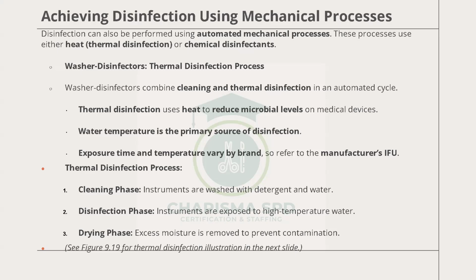Then after that is the rinsing stage. Based on the instrument you have in it, you can have what we call the milking stage, or the instrument milk stage. But orthopedic instruments don't have that. It's not allowed, mainly because of the implants. So if it's a regular instrument cycle, then we also have the lubrication cycle. Then after that, the rinsing stage comes in, and then the drying phase comes in. So basically, this is how these machines work.